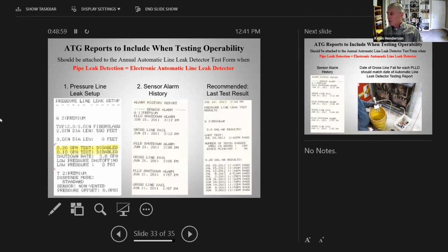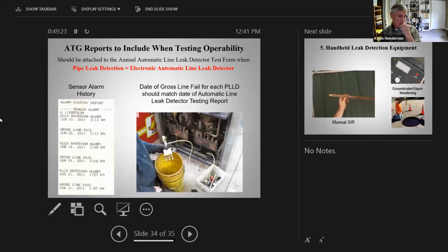There are a couple of different reasons for that. I'm not here to troubleshoot or pretend to be an expert on PLLDs, but it is very problematic to get an electronic leak detector to go into alarm sometimes. So it's very important for you to be able to show that you did cause it to go into alarm on the date that you did the functionality test. And again, there is the sensor alarm history, showing you that. And just reiterating, the dates should match, right? Yeah, they better match.